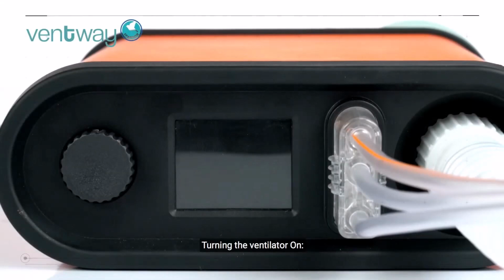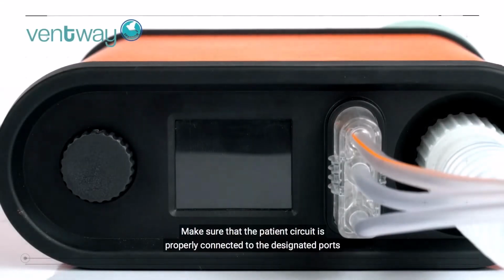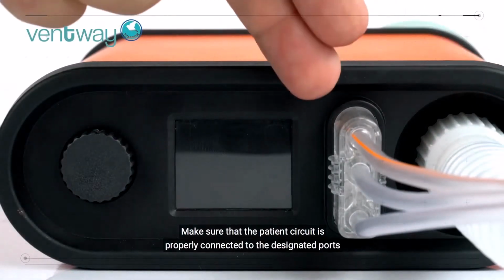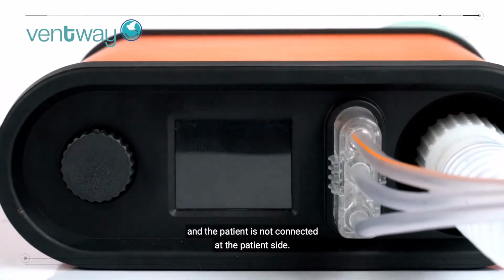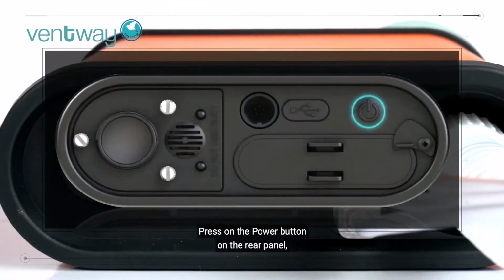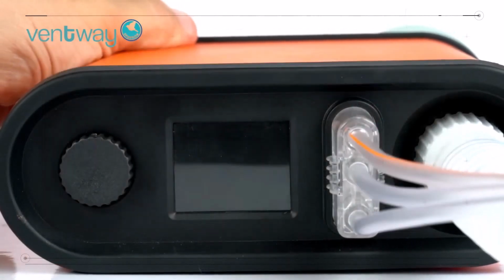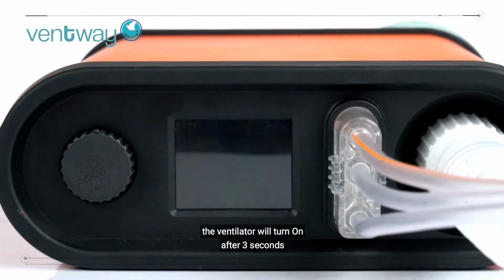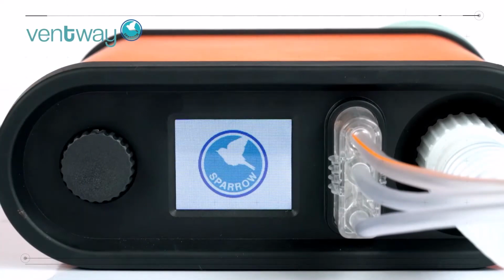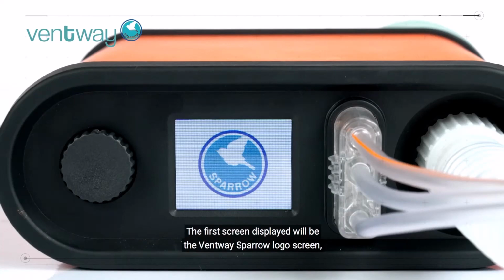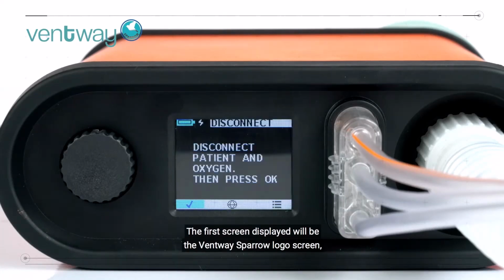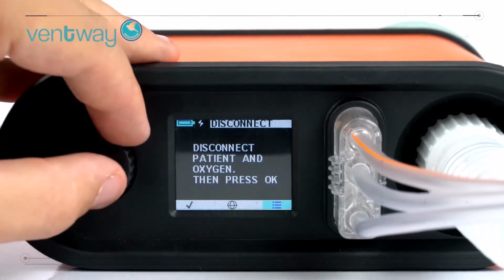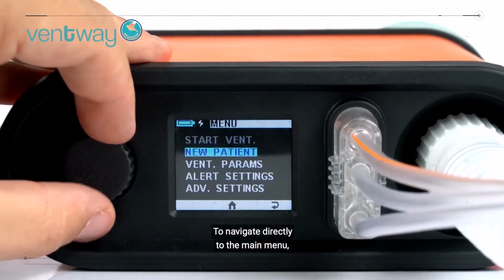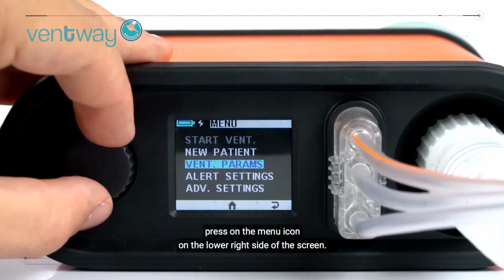Turning the ventilator on. Make sure that the patient circuit is properly connected to the designated ports and the patient is not connected at the patient side. Press on the power button on the rear panel. The ventilator will turn on after 3 seconds, and a voice indication will be heard. The first screen displayed will be the Ventway Sparrow logo screen, which will directly switch to the patient circuit test screen. To navigate directly to the main menu, press on the menu icon on the lower right side of the screen.